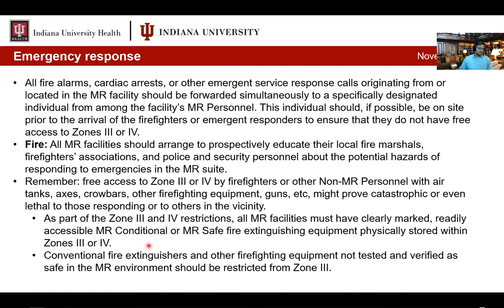Recall that conventional fire extinguishers and other firefighting equipment are not tested and verified as safe in the MR environment. They should be restricted from Zone 3. If you see regular fire extinguishers in Zone 3, you need to have them removed - they should not be in Zone 3.